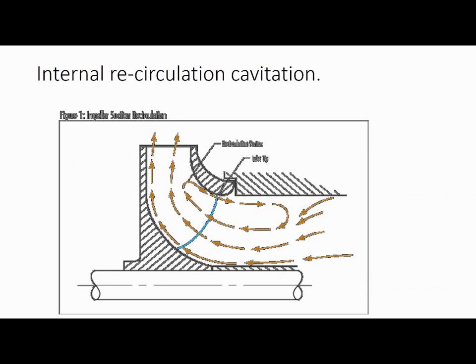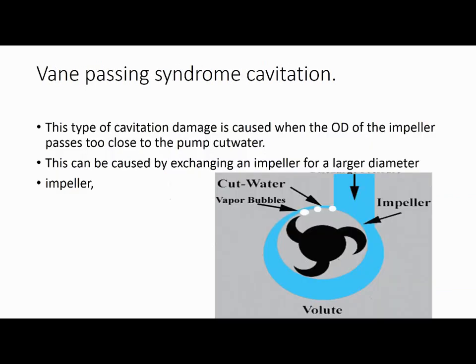Next is vane passing syndrome cavitation. This type of cavitation damage is caused when the OD of the impeller passes too close to the pump cutwater. This can be caused by exchanging an impeller for a larger diameter impeller.